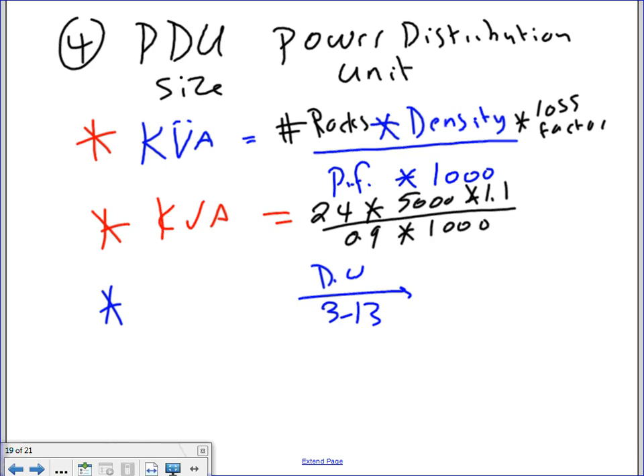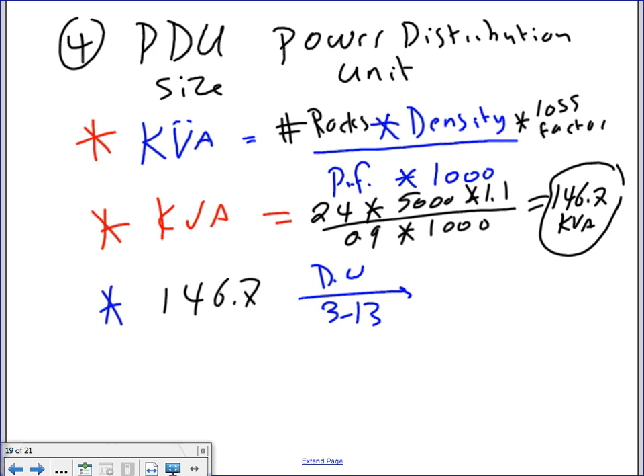So my friends will be happy here. What did we come up with, guys, here, please? 146.7. 146.7 kVA. Same calculation that we did for the UPS. And then, Karen, you're going to take 146.7 kVA to the table where I wrote them for you, and they will give you 160 kVA.